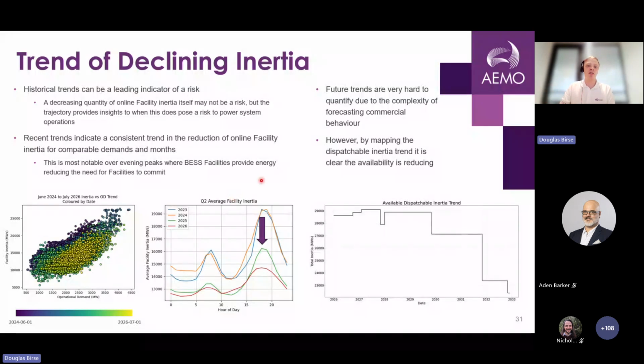One thing we wanted to test, in terms of confirming this isn't just because demand is decreasing — and Nick's demonstrated that's not necessarily the case — is shown in the figure to the left here: facility inertia on the y-axis, operational demand on the x-axis, with colored dots by date, from June 2024 to July 2026. You can see that for equivalent demand, the dots are grouping lower and lower as the colors change from blue to yellow. That indicates that as time has progressed, we're seeing a lower level of facility inertia for equivalent levels of demand. That means we're now serving demand with less facility inertia, which is either coming from renewable generation, or because battery storage is changing the dynamic of facilities participating and running on the power system.